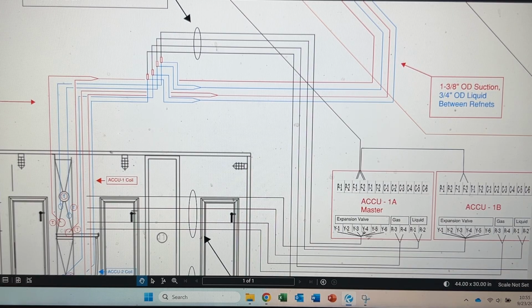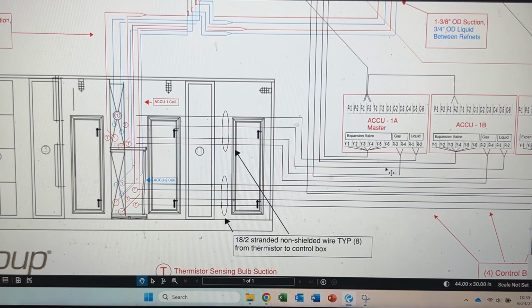So that ended up being just, again, like five wires terminated appropriately based on where they were required under the expansion valve at each of the control boxes. All right, so the other portion of this for the control boxes were the thermistors. Okay, so this is basically going to talk to the control box on the wall as to what inlet and outlet delta is. And what that'll do is send communication to the expansion valve on what it's to do as far as opening and closing.